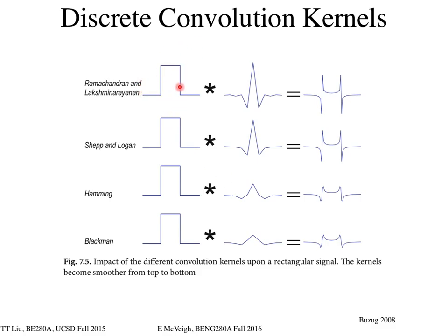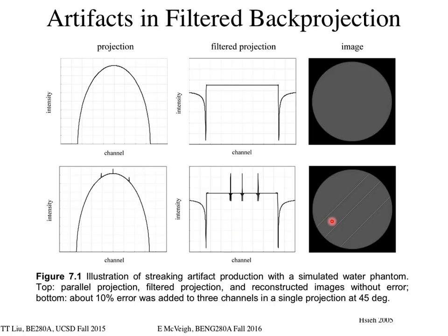If you reconstruct a square with the hard Ram-Lak filter, you see artifacts coming off the edges, but you get a fantastically sharp edge — high line pairs per millimeter. If you want a softer, gentler image with lower noise, you convolve with the Fourier transform of a softer filter like Hamming. This blurs the picture and reduces hard-edge artifacts. These are the digital versions of those filters — pretty simple to implement, and convolution kernels on any graphics computer can be executed essentially instantaneously.